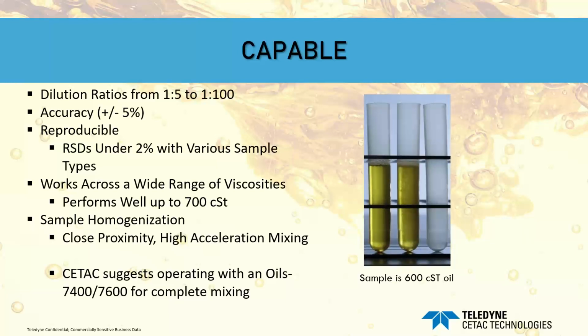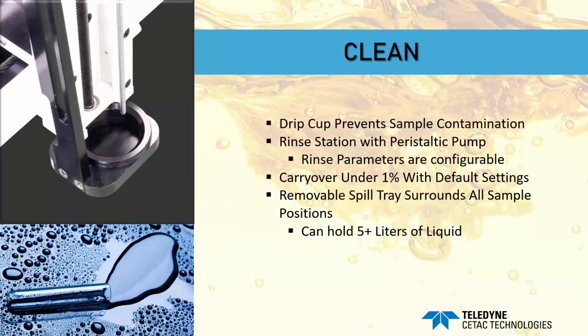Okay, and APS is also clean. It has a drip cup that swings under the probe whenever it is raised, so this prevents drips from contaminating your other samples. The rinse station is fed by a peristaltic pump, and with the default settings, you can achieve carryover of under 1%. Both the rinse parameters are configurable, so you have the flexibility to dial in the perfect amount of rinse for your method.